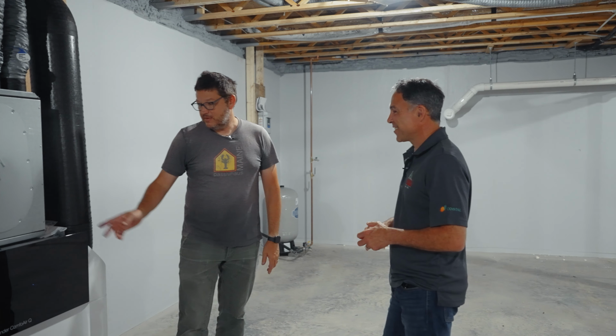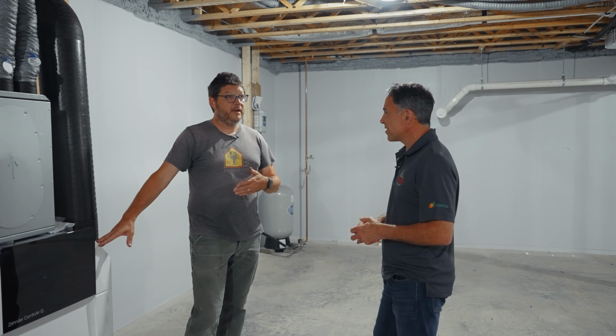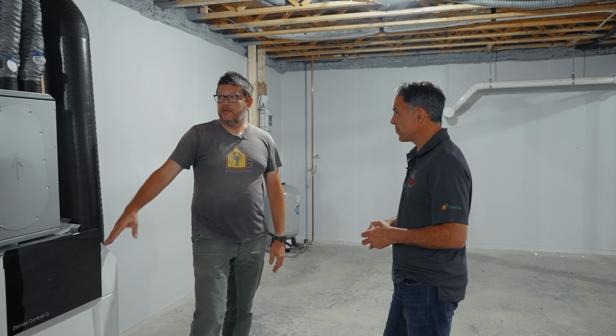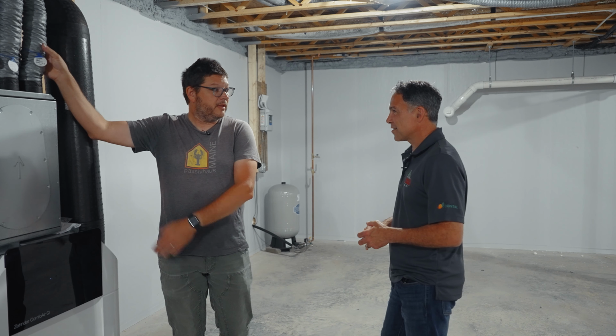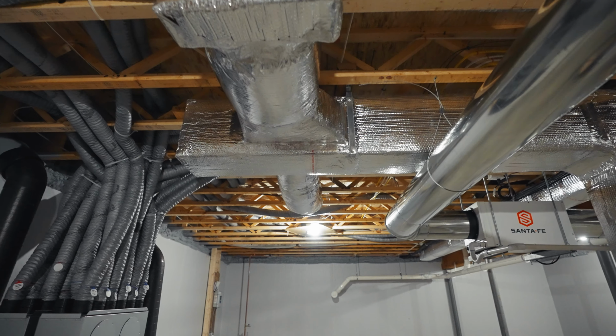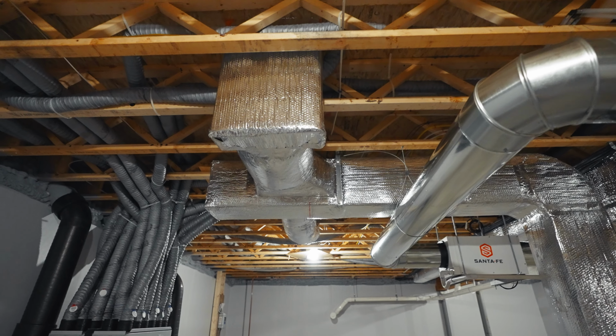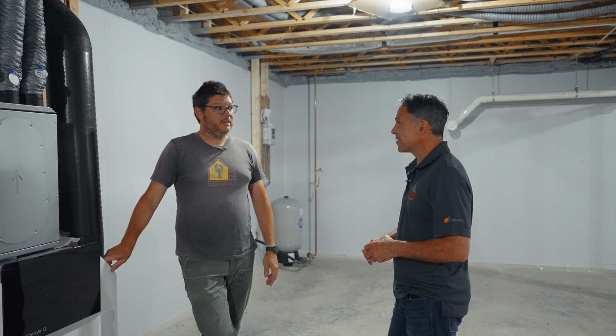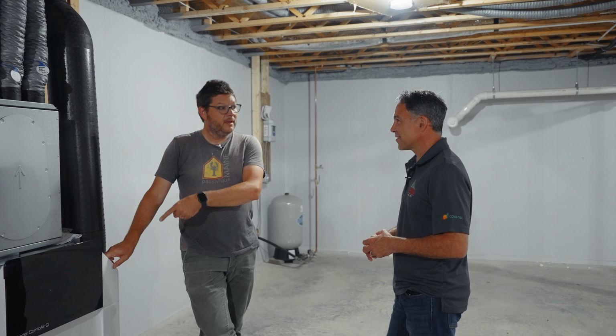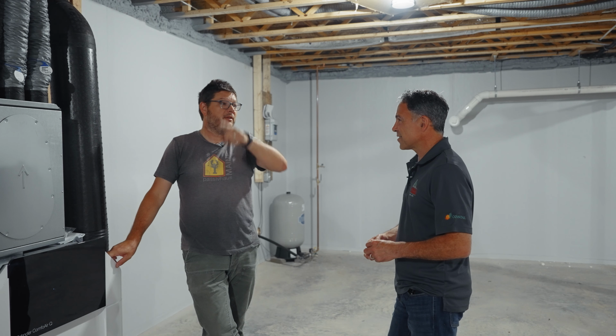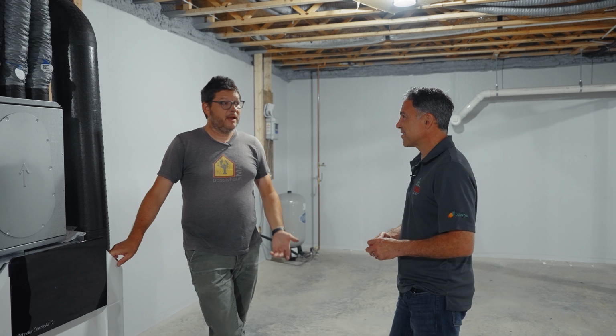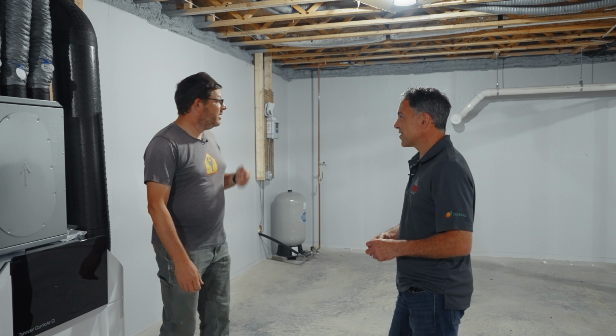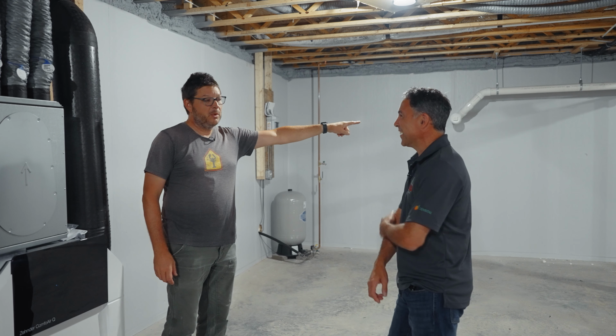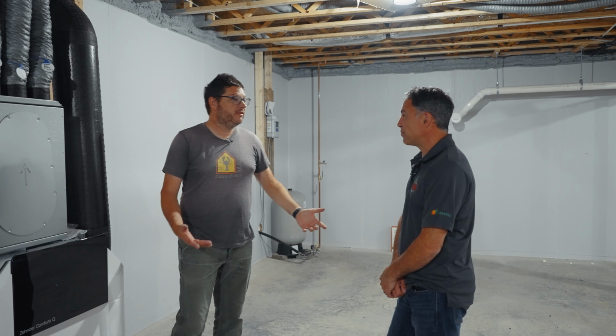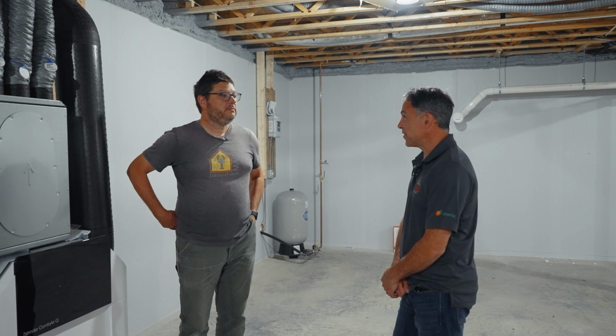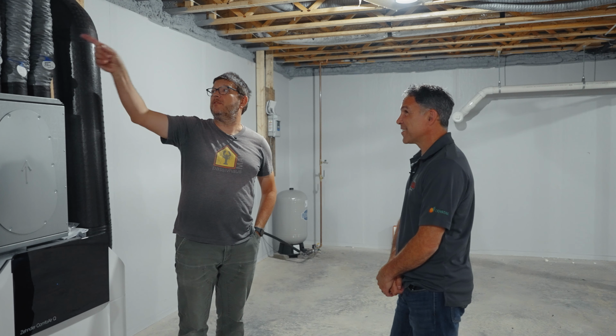The reason it doesn't work is this is designed to run at about 130 CFM, going through little tiny ducts because of that small fan and small duct. Meanwhile that other duct is huge, like 10 by 14, with a 600 CFM motor in it. So if you're trying to blow 100 CFM through ductwork designed for a 600 CFM motor, the air doesn't move. It's kind of like if I stand here and blow really hard, you'll never feel the air move on the other side of the basement—that's essentially what happens. But if you put it through a long straw, you feel it on the other side, because the straw is designed for the motor.